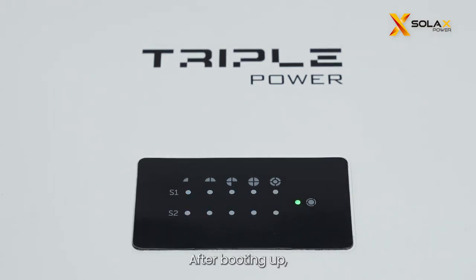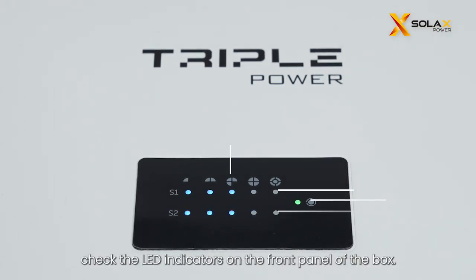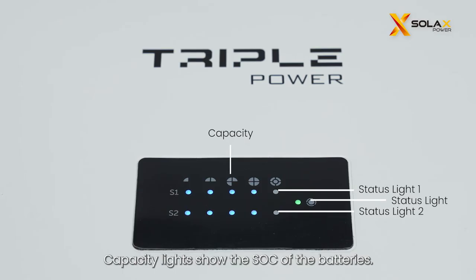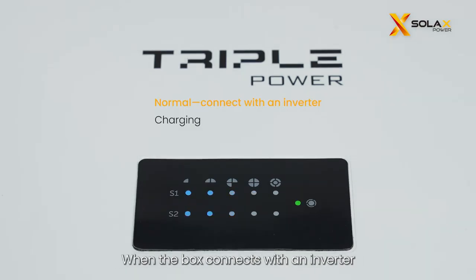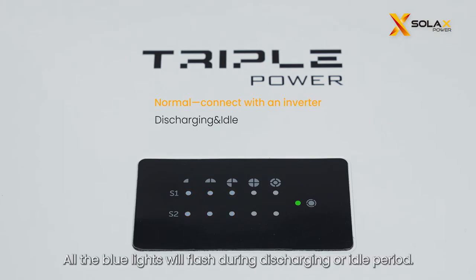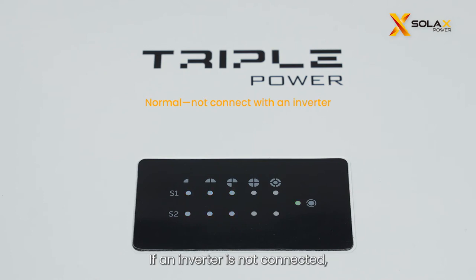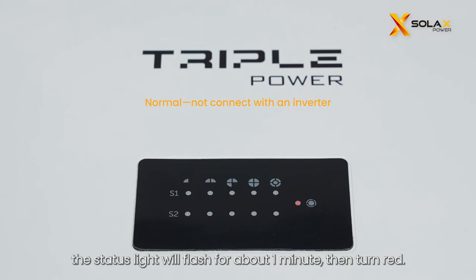After booting up, check the LED indicators on the front panel of the box. Capacity lights show the SOC of the batteries. Status light 1 or 2 flashing indicates a failure of the battery modules. When the box connects with an inverter and is in a normal status, the blue lights will flash in the last column during charging period. All the blue lights will flash during discharging or idle period. If an inverter is not connected, the status light will flash for about 1 minute, then turn red.